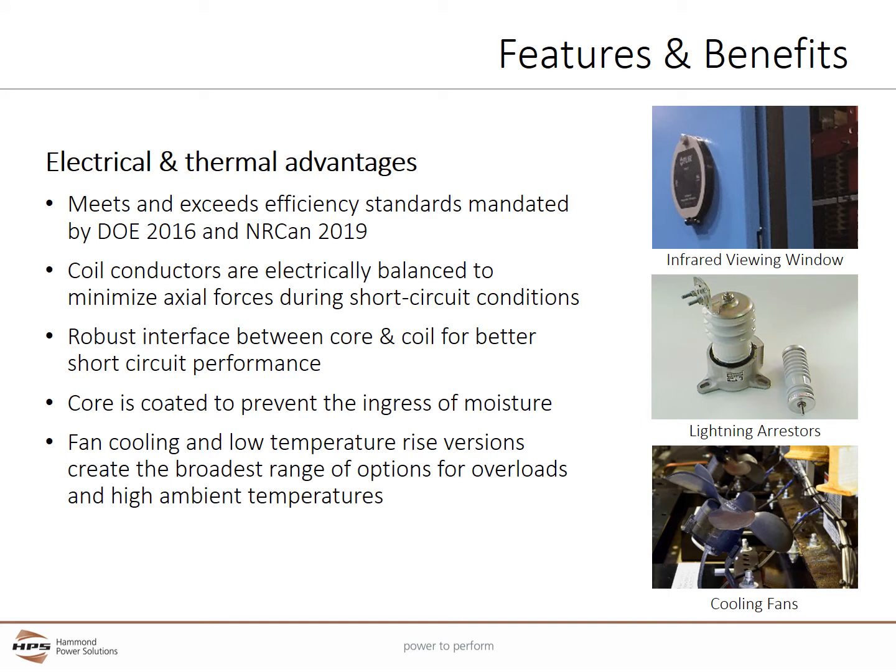VPI Transformers provide many electrical and thermal advantages. VPI designs meet the efficiency standards mandated by the U.S. DOE 2016 and Canadian NRCan 2019 regulations. The coils are precision-wound with copper or aluminum conductors that are electrically balanced to minimize axial forces during short circuit conditions. The VPI design has a robust interface between the core and coil for better short circuit performance and mechanical strength. The core is coated with a varnish to prevent the ingress of moisture. Fan cooling and low temperature rise versions create the broadest range of options for overloads and high ambient temperatures.